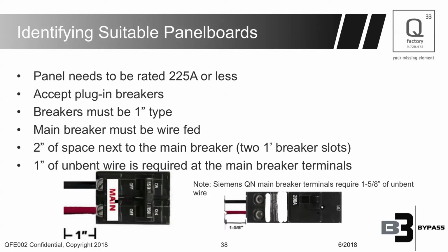The panel board must accept plug-in breakers. Again, we're going to plug it in, not for the electrical connection, but more for the mechanical connection. So this is mechanically secured within the panel. It must accept 1-inch breakers because we use a 2-inch format quad breaker. So it needs to accept 1-inch stab-in breakers.